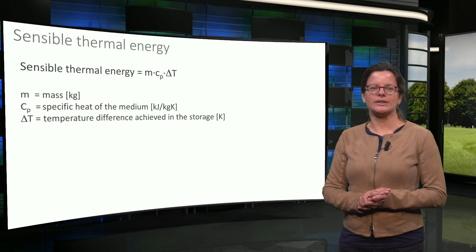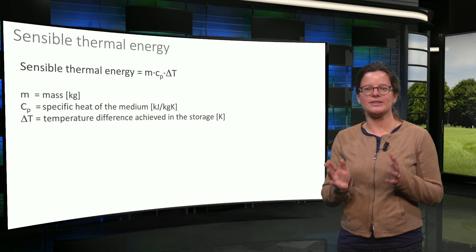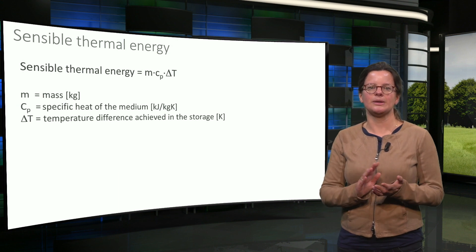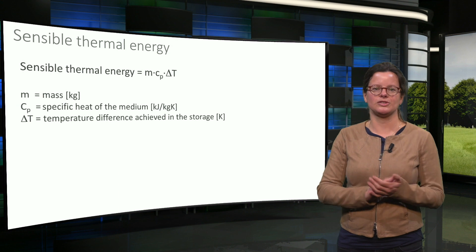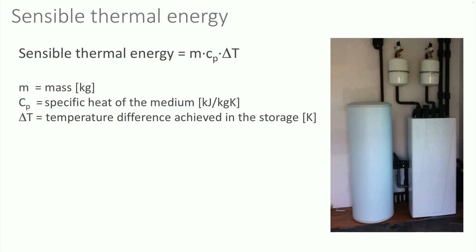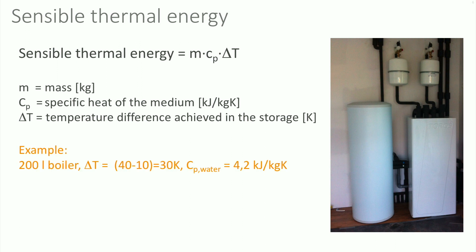The amount of sensible heat stored is calculated by multiplying the related mass with the specific heat capacity and temperature difference before and after the storage is charged or discharged. As an example, the thermal energy stored in a hot water buffer is shown. The boiler has a volume of 200 liters and the temperature is raised with 30 degrees Celsius. The specific heat capacity of water is 4.2 kJ per kg·K.